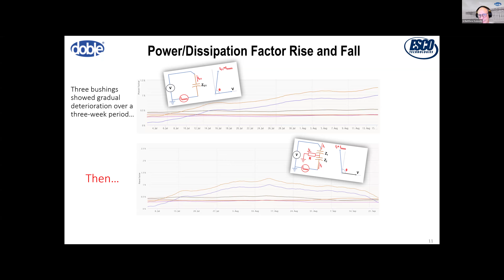In the end, what they found was that the O-ring adapter at the very top of that bushing had become corroded and damaged. Water was ingressing into it, causing contamination to build up along the edges, and some overheating material was developing as well, which was creating that anomalous value.